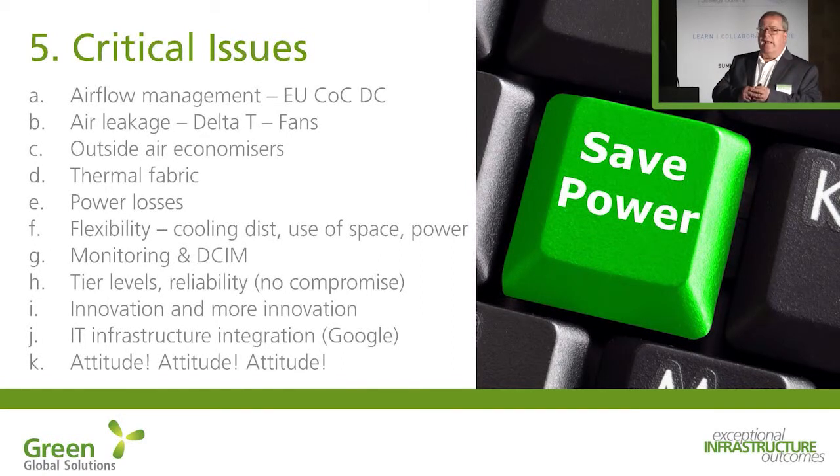So typically in an older data centre, say you've got 500 kilowatts of cooling, it'll be set to 500 kilowatts of cooling, even though it might only need 200 kilowatts, but it still produces 500 kilowatts of cooling. Whereas with pressure management, we say, okay, aisle 2, we need a whole lot more air, the pressure differential goes beyond 20 pascals, please increase the fans, we need some more volume of air, please. Out it comes, and we provide air on demand, and that means we provide 500 kilowatts of cooling for 500 kilowatts of genuine IT load. If the IT load is 300 kilowatts, then we'll cool 300 kilowatts. That's what it's designed to do.